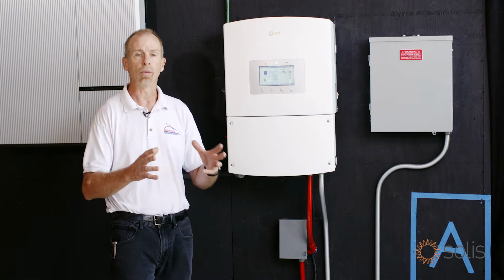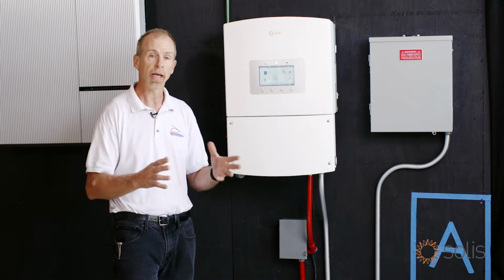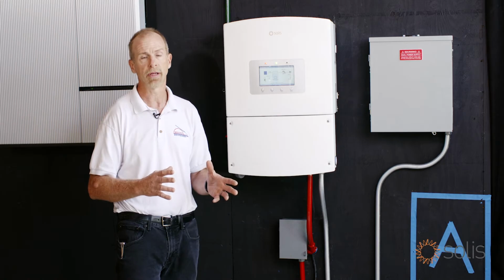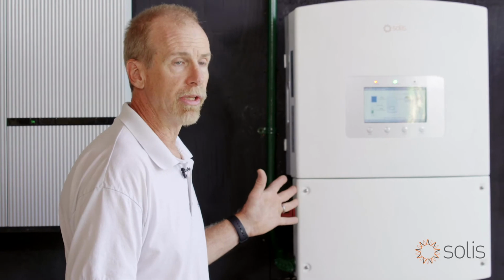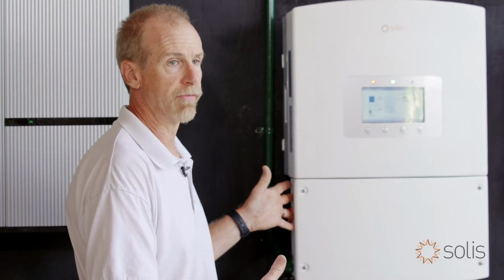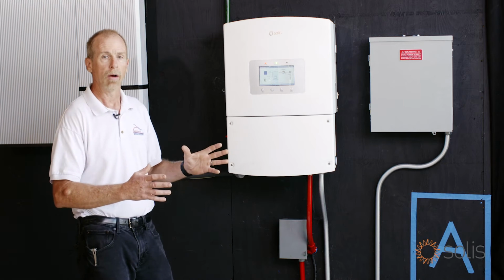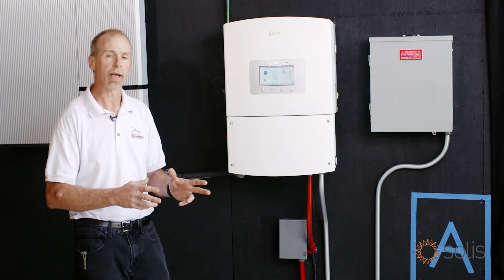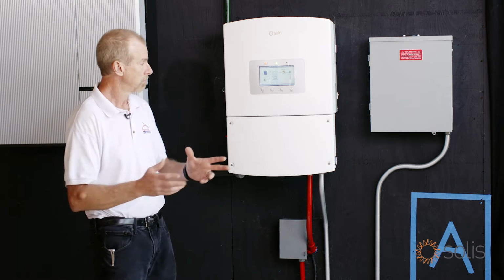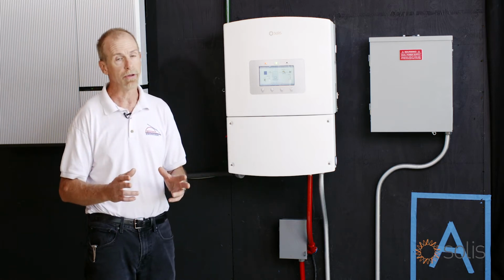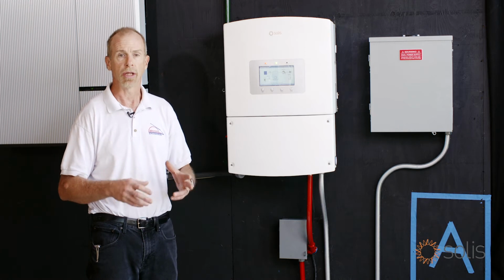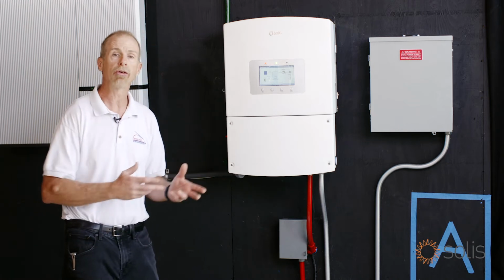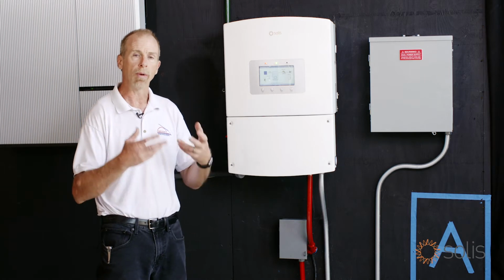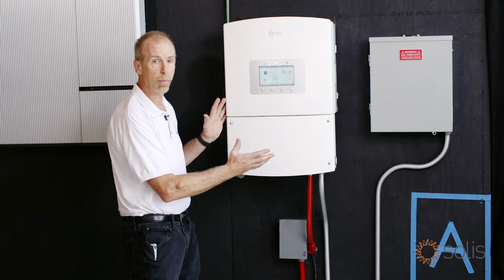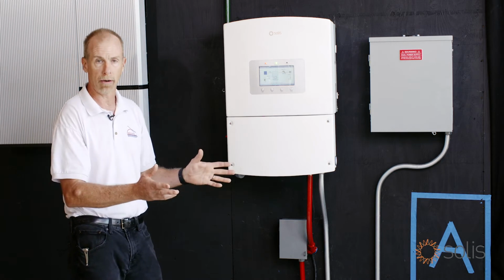And because of that, we need to make sure that we get these things set up properly and we have the proper components involved. One of those components is the auto transformer. The inverters that we're using these days are 240 volt single phase inverters. That's great, okay? Well, how many of the loads that we're going to operate off grid when the power goes out are 240 volt loads? Very few, if any, in many cases. The loads that we want to operate are going to be 120 volt loads. Really important that we have something that can take the 240 volt power and turn it into 120 volt power.